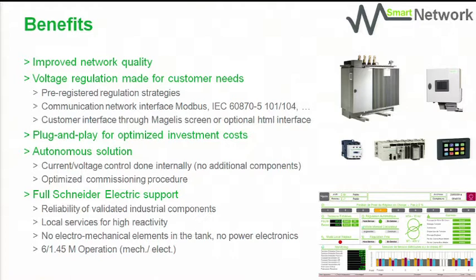What are the benefits of the solution? Looking at the photos of the different elements in our transformer, you will most probably see things you already know. There are standard active parts, a contactor on the lower side used for tap-changing, an electronic part which is a PLC — a standard Schneider PLC called Modicon — and a human-machine interface which is a Magelis screen, again a Schneider Electric product. What you don't see is a tap-changer.